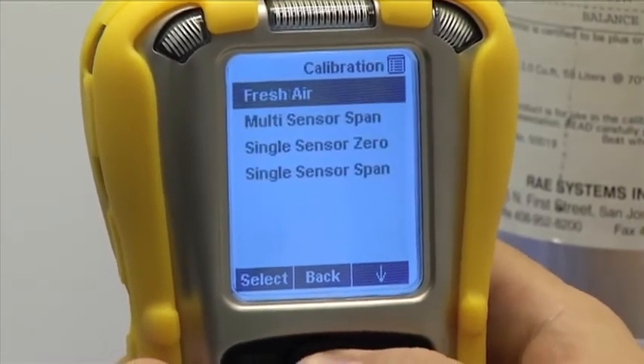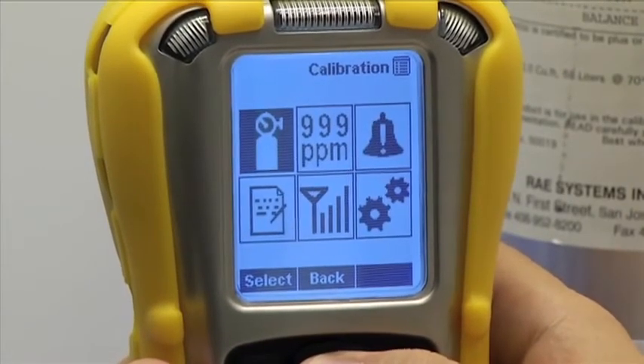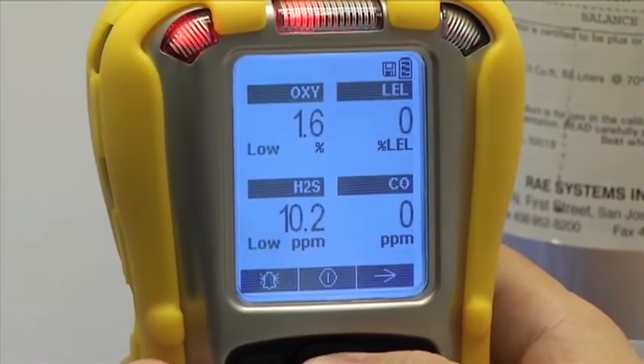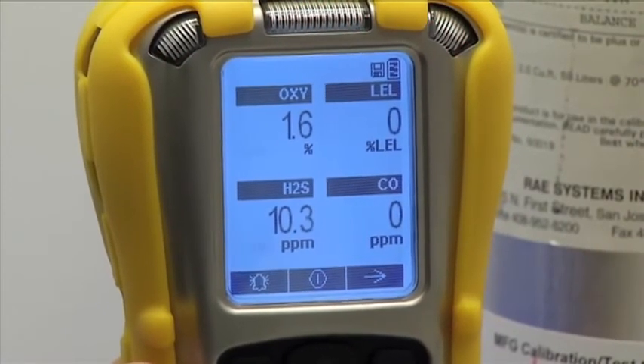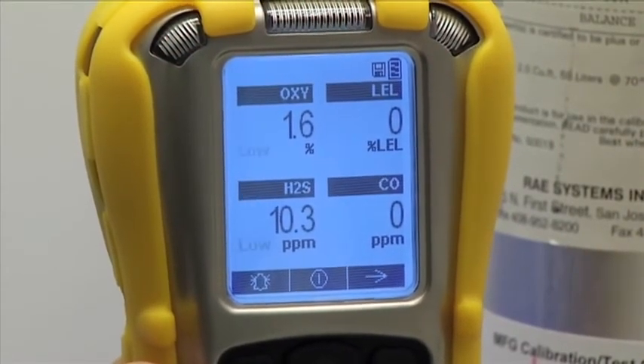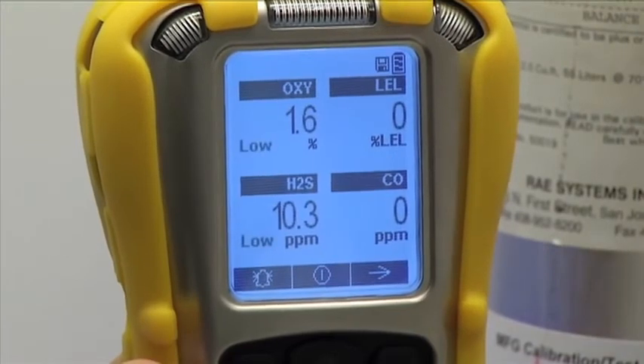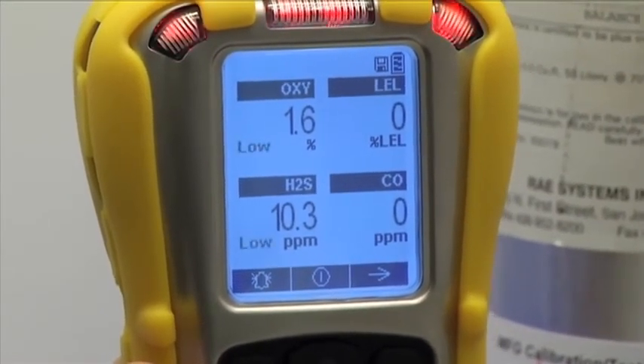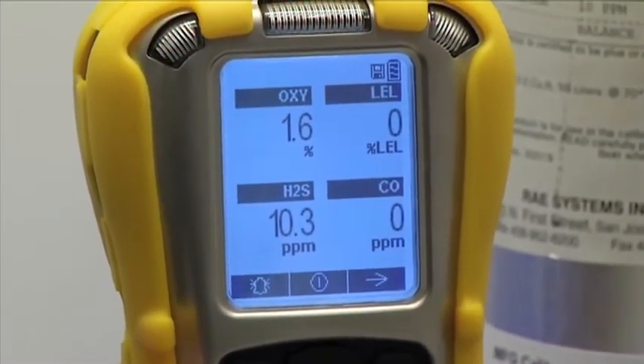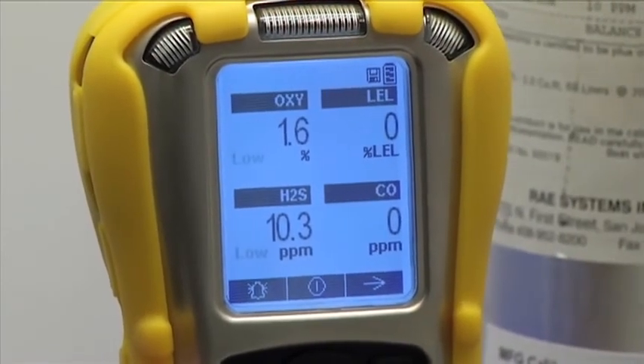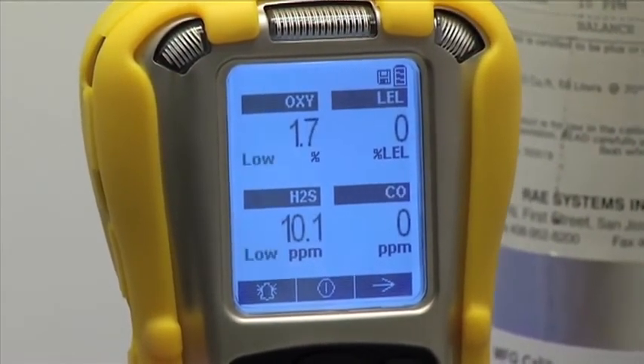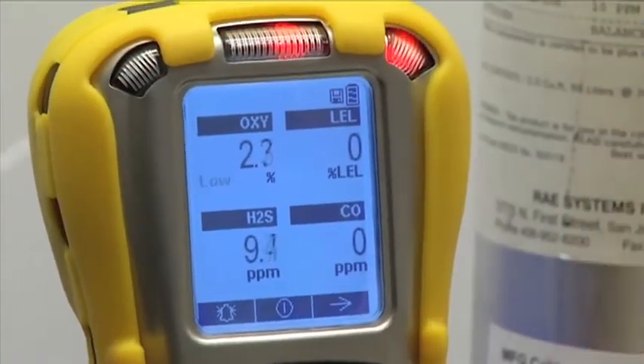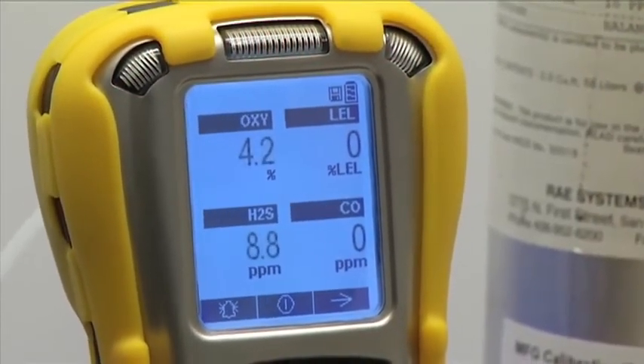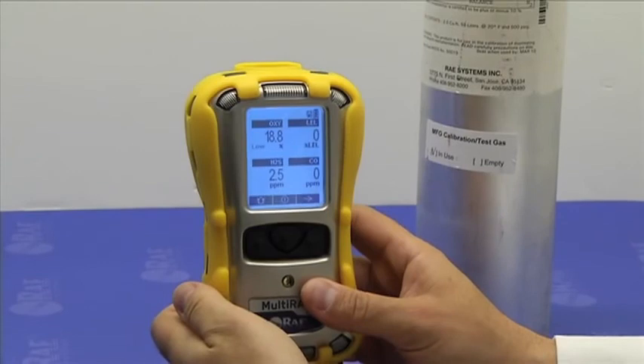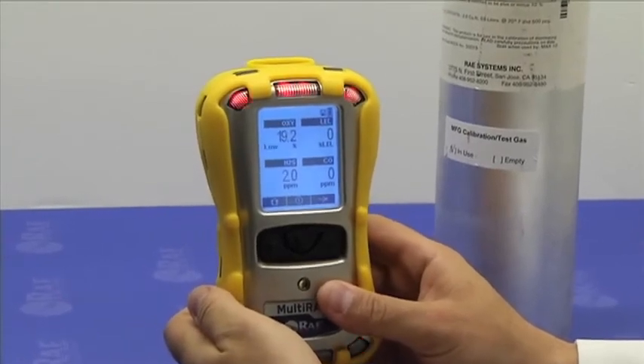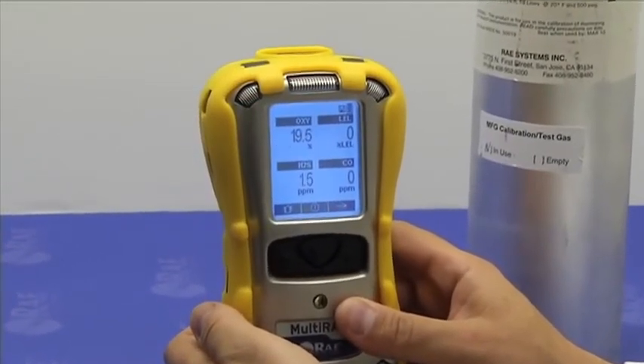When the span calibration process is complete, I can press the Mode button repeatedly to get to the main measurement screen, and we'll see that the instrument is in alarm still because there is still calibration gas present. So I need to turn off the calibration gas and disconnect the instrument from the calibration gas cylinder. The instrument readings will go back to normal once the calibration gas gets out of the system.